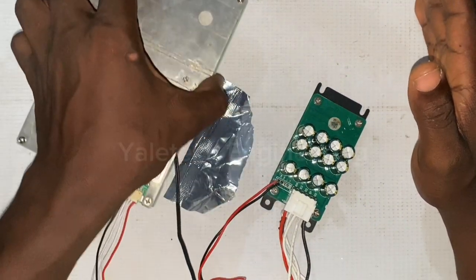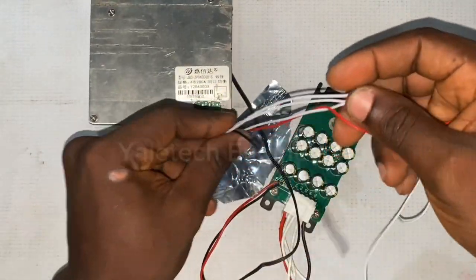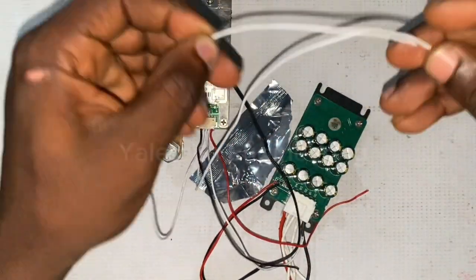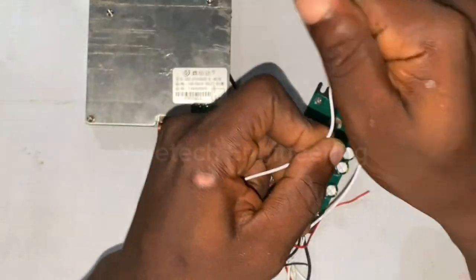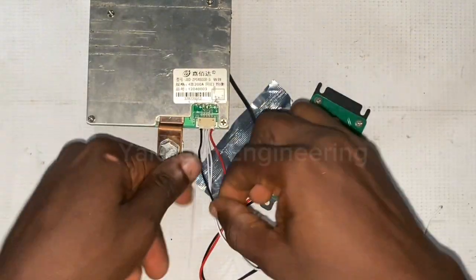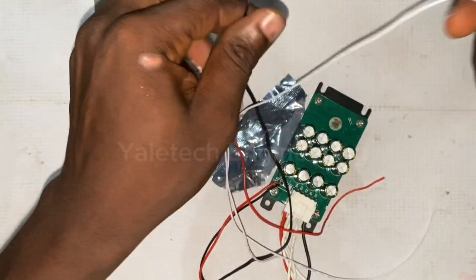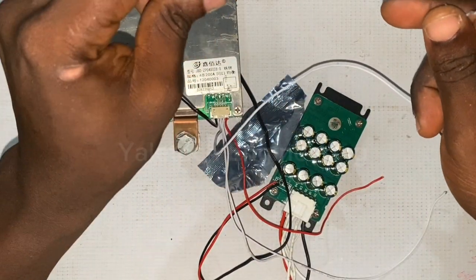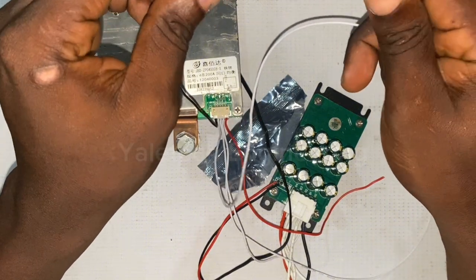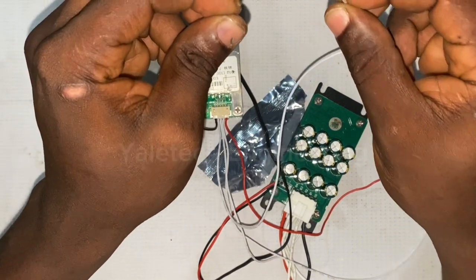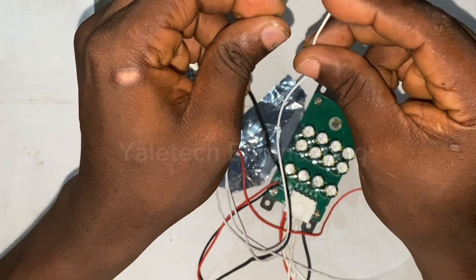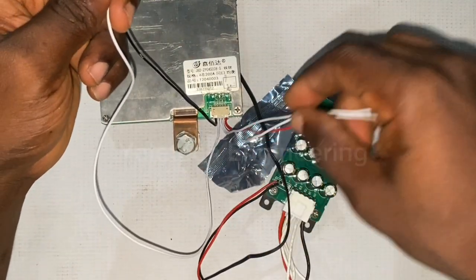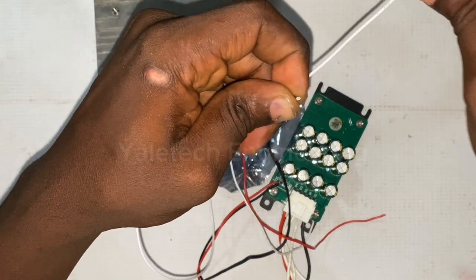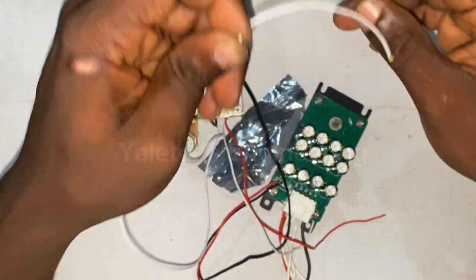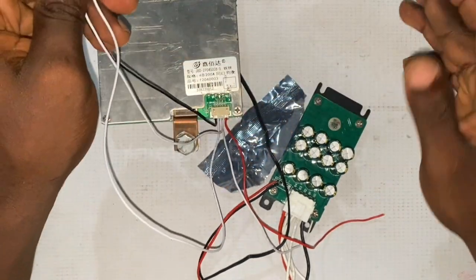The way the BMS works, this wire you see is more like a sensor - that's why it's not thick like the 6mm wires, it just dictates the voltage on those terminals. So once this area, say 0 volts, reaches 4.2, it assumes everybody has gotten to 12.2. That's why sometimes your battery stops charging at maybe 11.9, sometimes 12.0 - it will just stop.